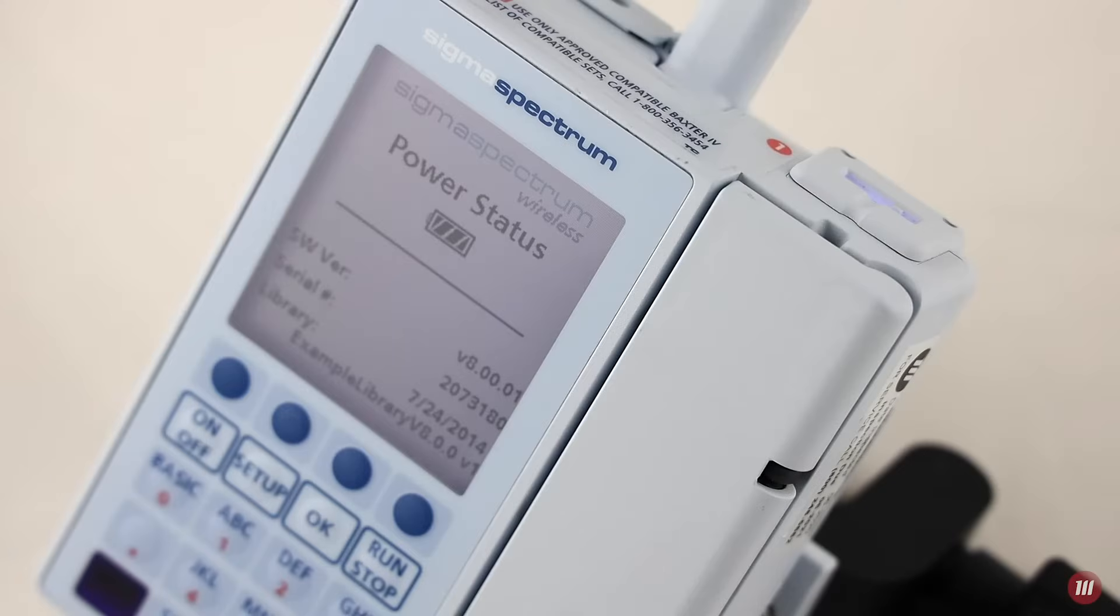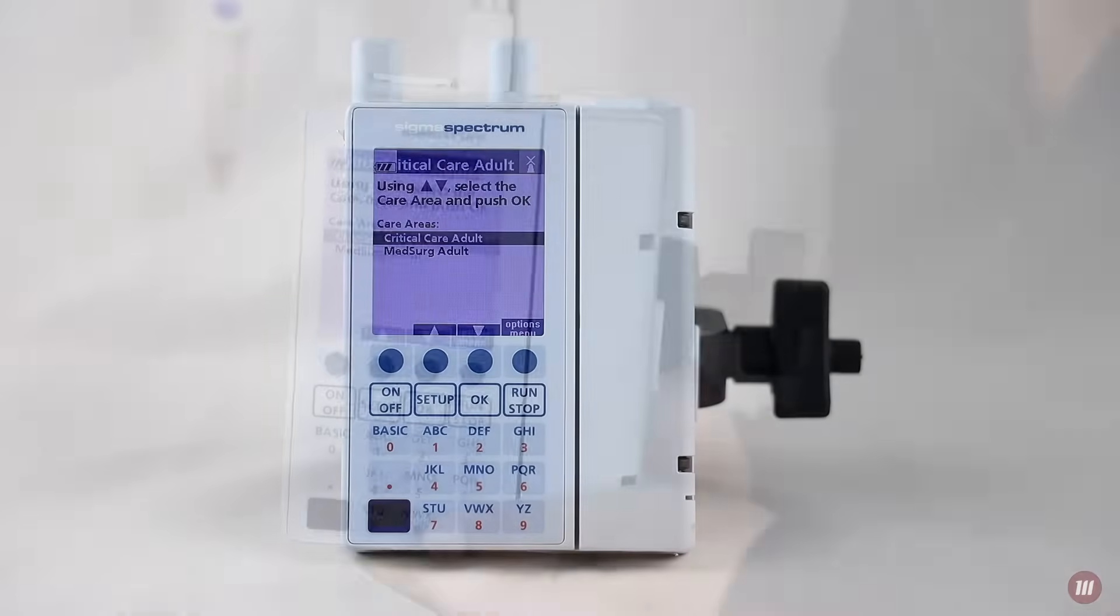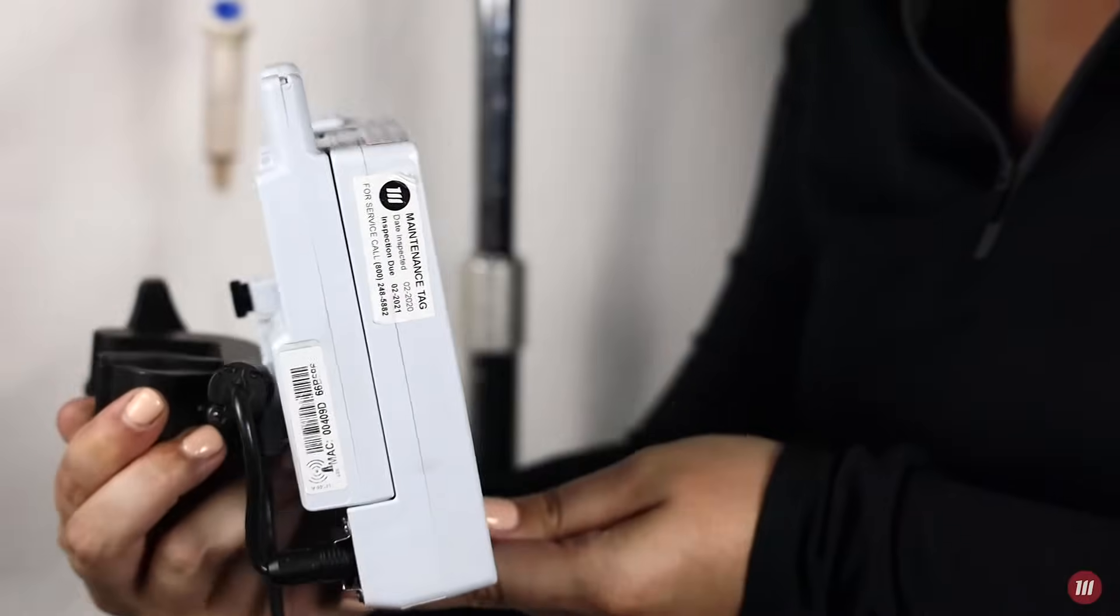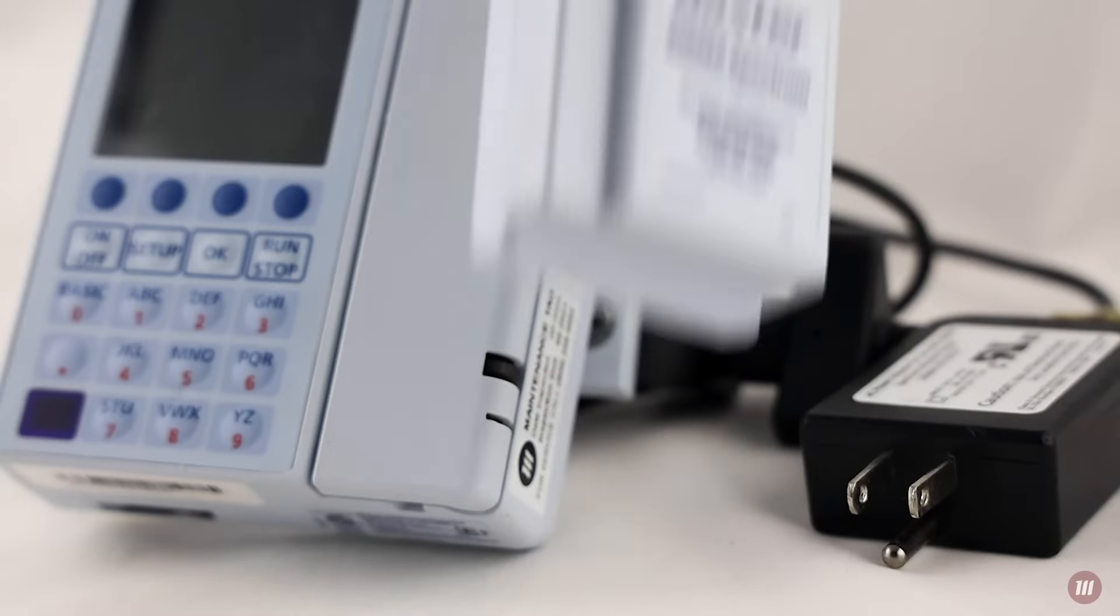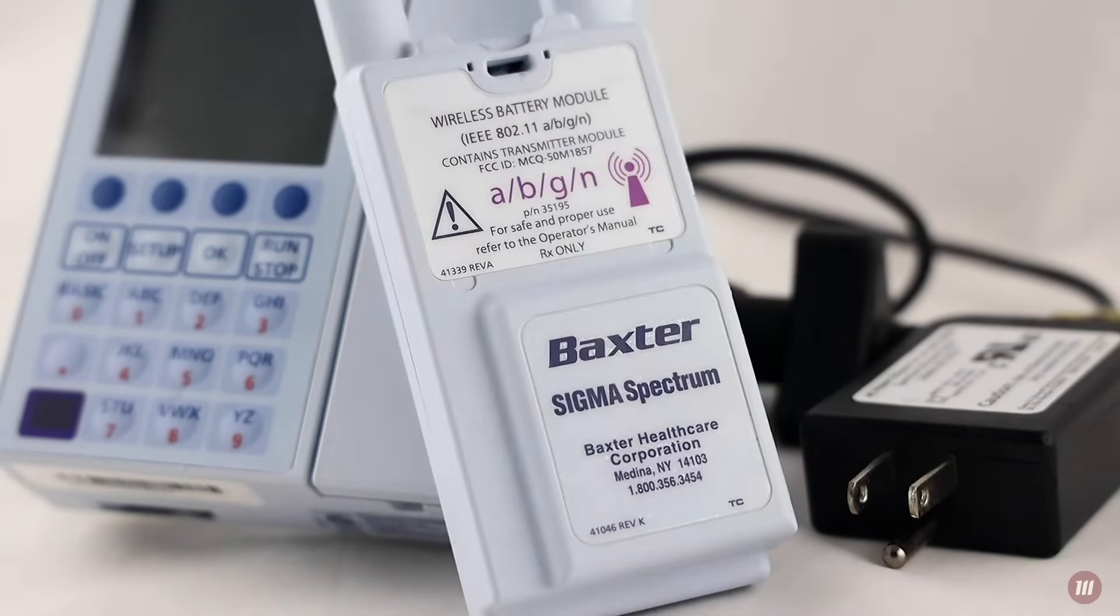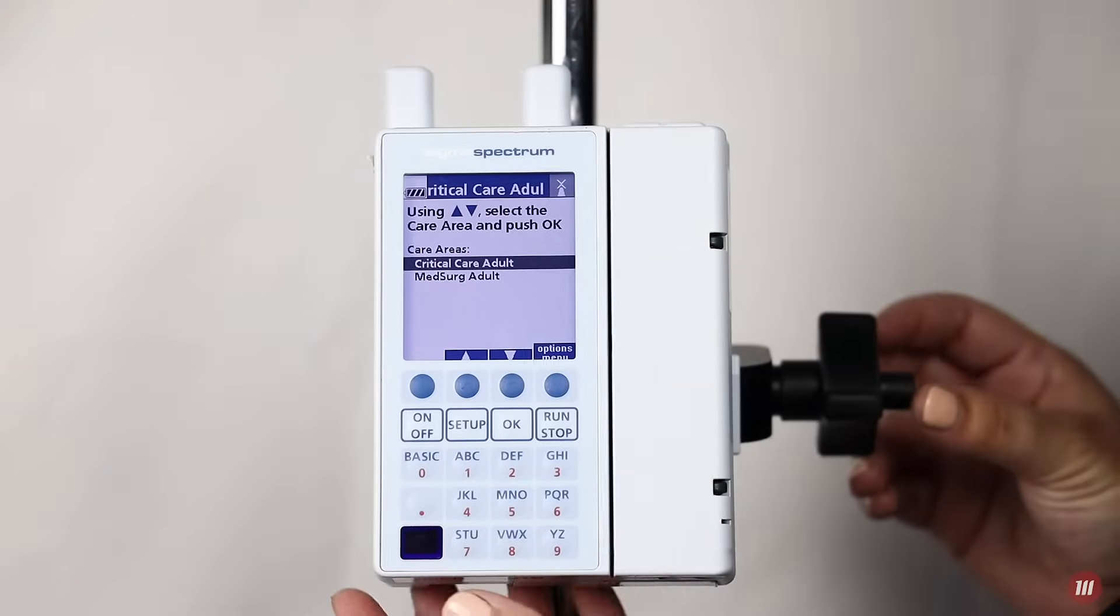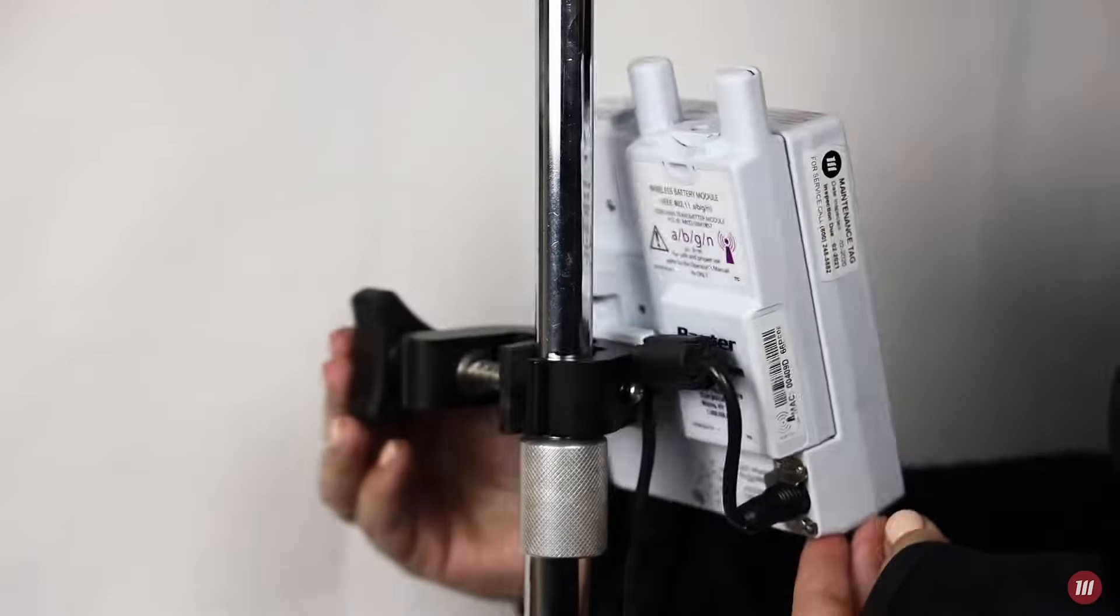The Sigma Spectrum infusion pump manufactured by Baxter is ideal for acute care hospital settings. The pump is small, lightweight, and mobile, which makes it a popular choice for many healthcare customers. It has an outstanding battery life that lasts up to eight hours. It can easily be mounted to an IV pole for use when transporting patients.